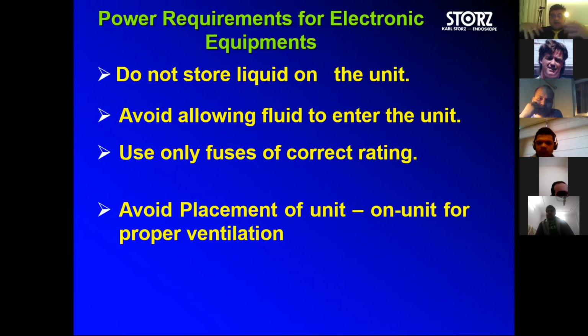So while you use a cautery, many times, especially in urology, they say, when I use cautery, I see lines coming on the video monitor. Now, this line is happening because of this electromagnetic induction induced by having one unit above another. When you put a gap, you separate it out, or your cautery is very close, or you have put in one phase. Normally, you have a three-phase connection to take a bigger load. Some operation theaters, small hospitals, B-tier, 3-tier cities, have single phase, in which you are connecting all your units like your camera, your monitor, your light source, and also the cautery.